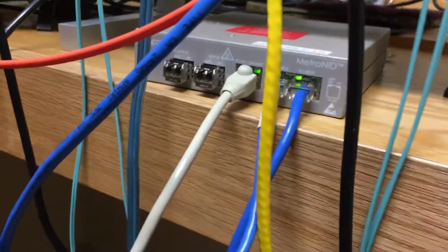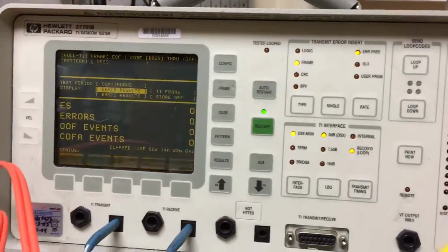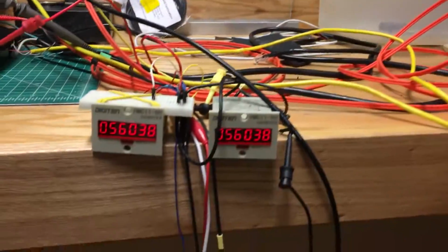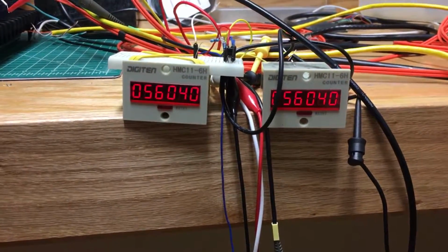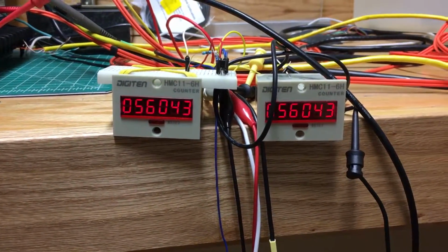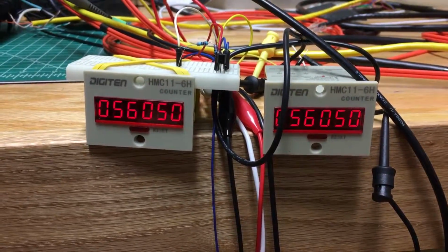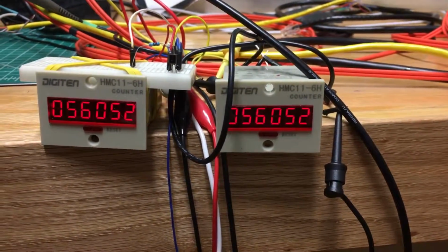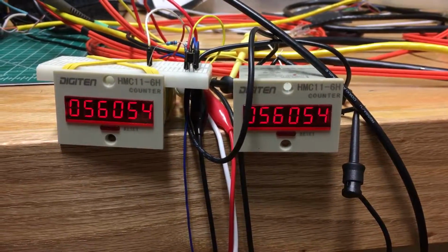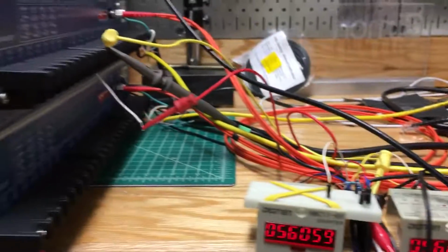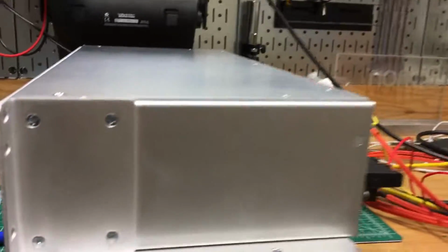Here's an Ethernet test generator, as well as a T1 tester, and this has been running overnight. As we can see here, we're up to 56,000. The left counter is the DTT input that comes from a generator, and we have 56,000 or so trip inputs, and if you look at the output, it matches 100%, so no trips whatsoever have been missing. Now, if you remember, this back-to-back application was within 5 milliseconds.